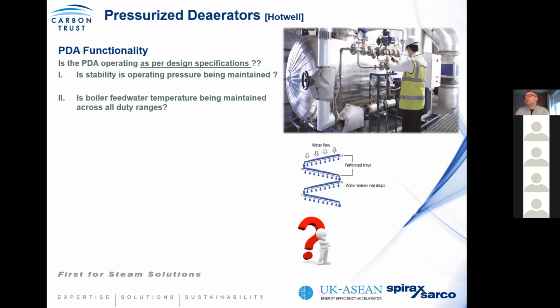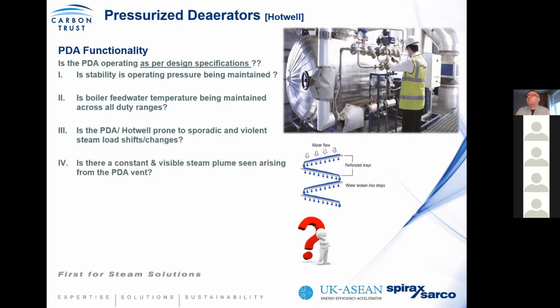Is boiler feed water temperature being maintained across all duties? What I mean by all duties is your boiler demand, your steam demand. So in other words, are you finding that if the steam demand goes up, your boiler feed water temperature reduces? Is the feed water tank or PDA prone to violent shifts, or does it vibrate at times? So in other words, do you find at times there's too much energy, and too much energy means you get kinetic energy and it starts vibrating, and you see a lot of losses to atmosphere. And then at times you find it just sits there and it's very quiet. So again, it's understanding how the system operates. Is there a constant visible steam plume seen from the vent? Do you find you have too much steam, or no steam at all?